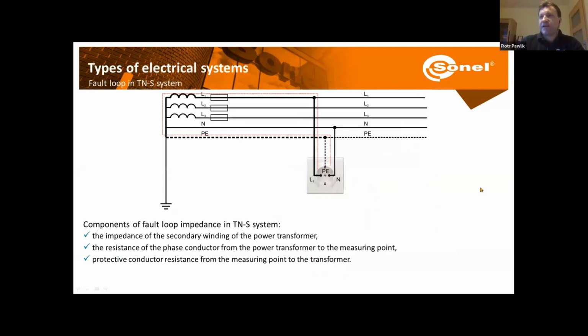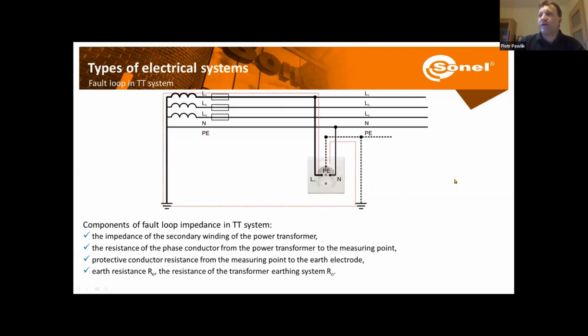Okay, and here we have some examples of the fault loop. So we have a fault situation and our loop with the current flow. Here it is. So that's in case of a TN system, it returns through the PE channel. So that's in the wire in the wall directly to a transformer. Or in case of a TT system where the grounding is local, then the loop will close through the actual earth, actual ground.